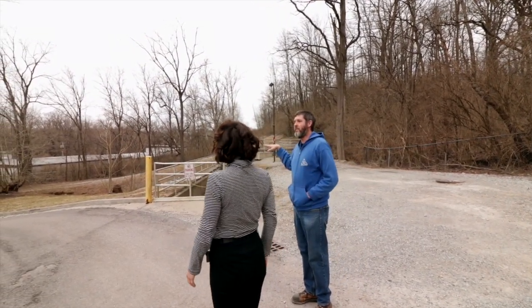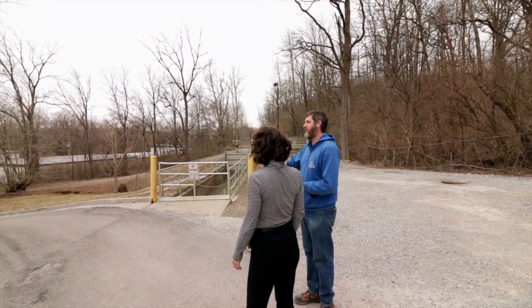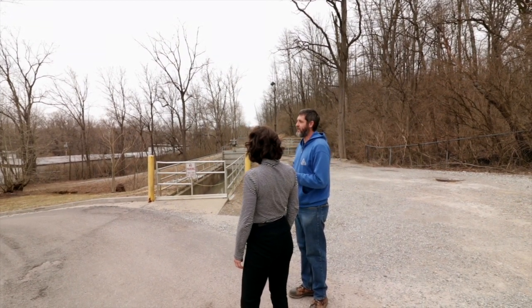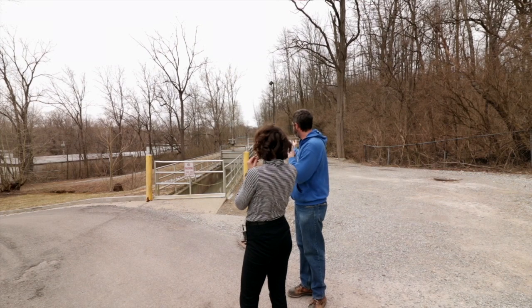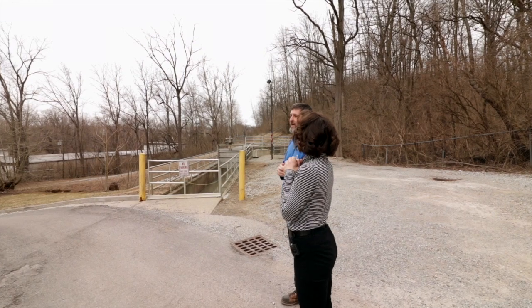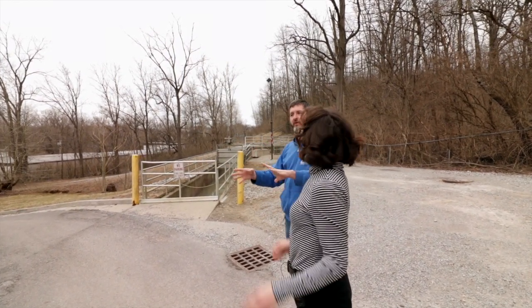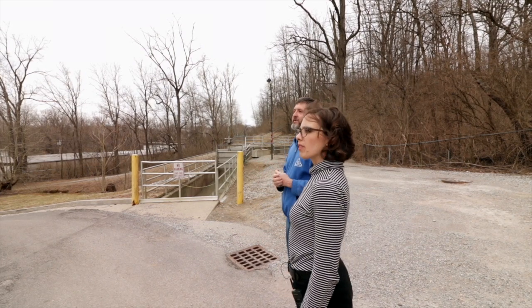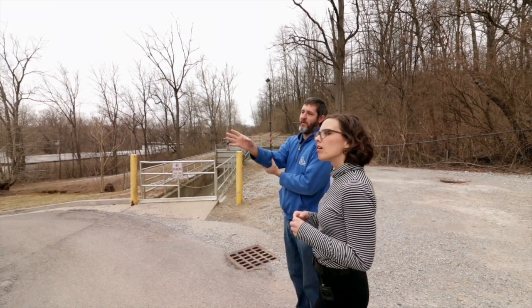When the water comes in, they break it down into preliminary treatment, primary treatment, and secondary treatment. We're a facility that also has tertiary treatment. For the collection side, the sewers are designed to flow at two feet per second, which keeps everything suspended so it travels all the way to the facility — you don't get sediment buildup. That's the typical design.